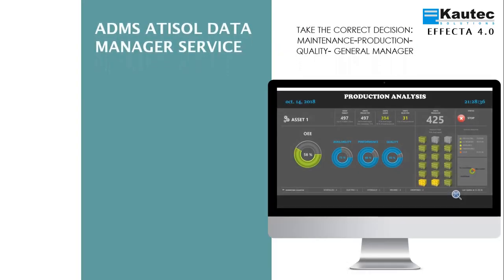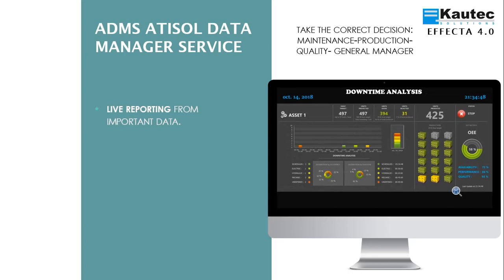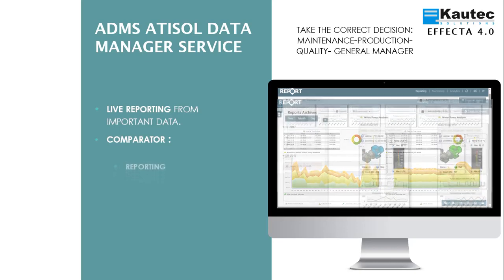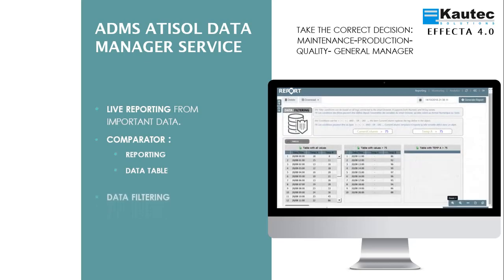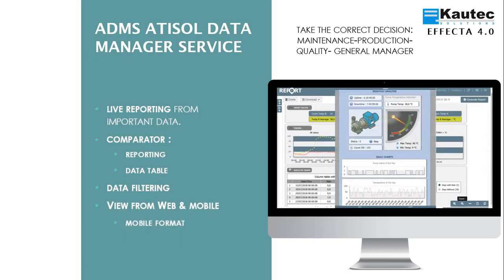ATISOL Data Manager Service is the application to make the right decision for maintenance, production, quality and management. See live reports of the main data for production, maintenance or quality. Compare data such as the deviation between the theoretical measurement of bolts and the real one, and compare it across different months or days. Compare machine consumptions in different months or days — for example, the electrical consumption of the press or gas in the ingot furnace — or compare tables of data to see differences across different days, months or periods. For example, to know the real cost of energy, electricity or gas for each ton of profile in a given die, and compare it with different productions over time. Filter data to see the trend — for example, to see that a furnace tends to consume more and more gas per ton in a given die, indicating that a furnace revision must be carried out. All information is also accessible through mobile devices or via web on PC.